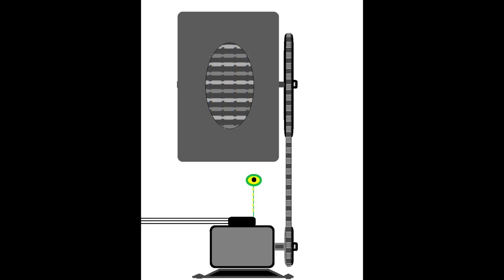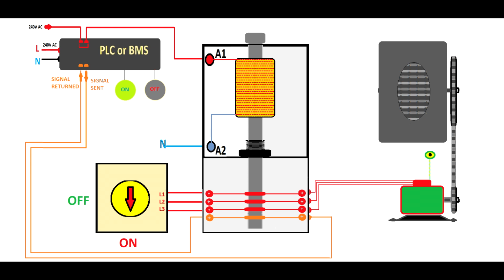Let's talk now about these fans. Now this is the way you will see the fan. I just made a little gash in that fan box so you can see how the fan is turning. Now you will see, you'll enable these fans, and the contactor has 4 switches. 3 of them, L1, L2, L3, are the power circuit, and the last one, which is orange, is an auxiliary switch which actually will return the signal into this programmable logic control.